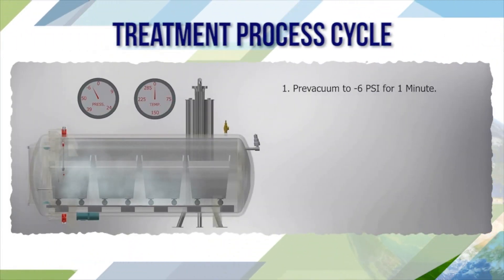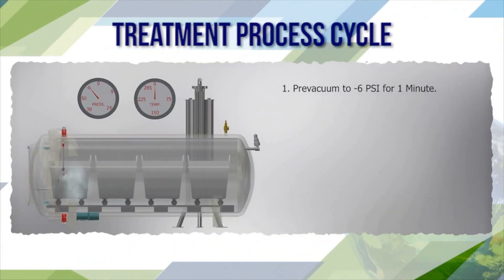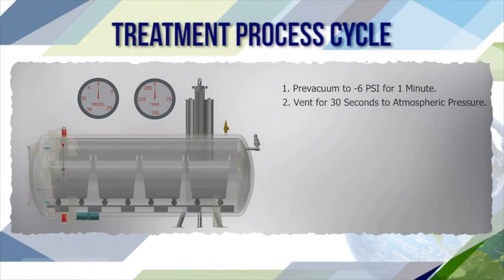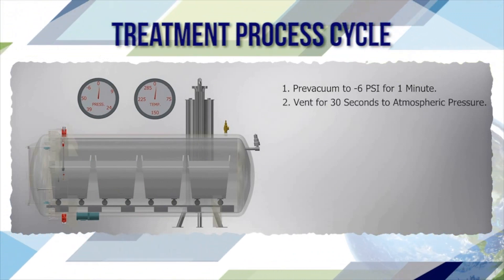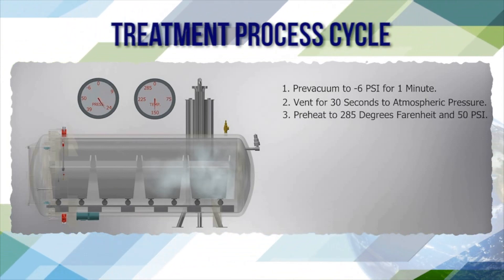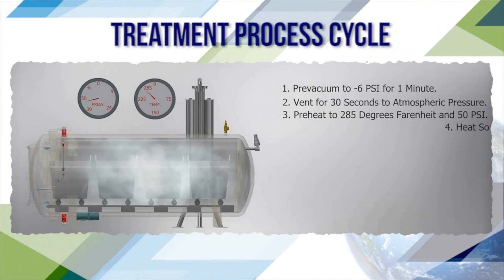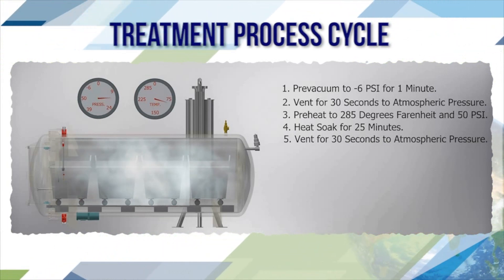Treatment process cycle: pre-vacuum to minus 6 PSI for 1 minute; vent for 30 seconds to atmospheric pressure; pre-heat to 285 degrees Fahrenheit and 50 PSI G; heat soak for 25 minutes; vent for 30 seconds to atmospheric pressure.